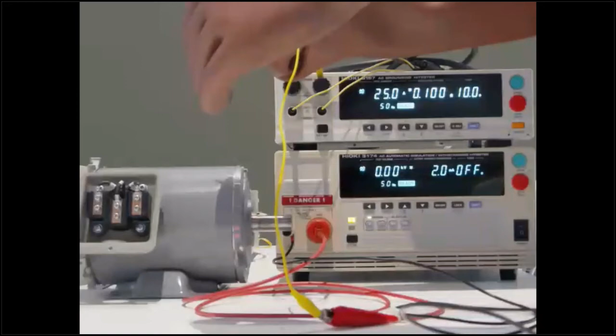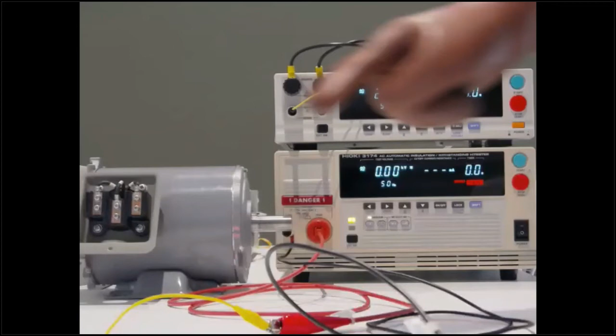Before measurement, please check the connection. Because if the wiring is open, the measurement has no meaning. So please check that the wiring is okay or not. Like this, this is a short, so this connection is okay, and you can connect to your device.